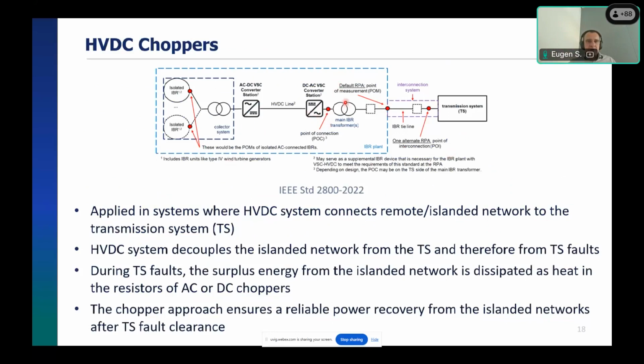What we see in the market is HVDC systems connecting remote islanded networks to transmission systems. In some cases this involves offshore wind farms or remote generation, which can also be onshore located, but it's always an islanded network. The HVDC system decouples the islanded network from the transmission system, and therefore from transmission faults, so if a fault happens, the islanded IBRs do not see it and continue operation.